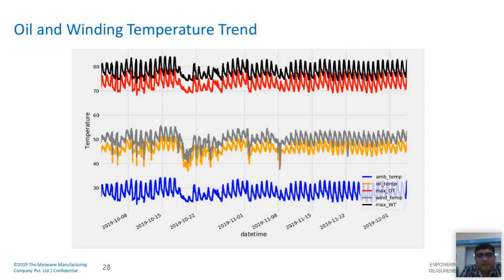Now you see two more curves, which are the limits of the maximum oil and winding temperature that should be allowed. Typically, in terms of protection, the OTI and WTI settings are fixed at particular temperatures based on standards, and as per the recommendation of the OEM based on their design evaluation. But as we understand, heat generation is a function of loading and the losses within the transformer. Heat recovery is also a function of the cooling technology, the cooling method, as well as the ambient temperature. So here you see varying limits, and these can also be customized based on recommendations from the OEM or user.